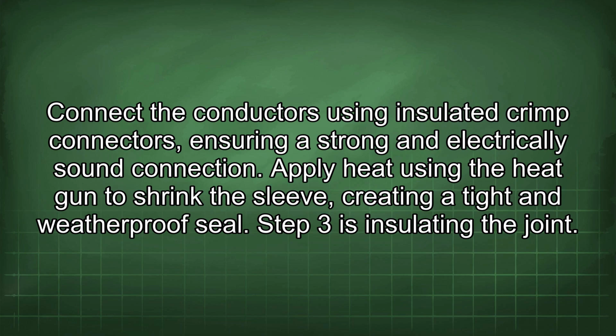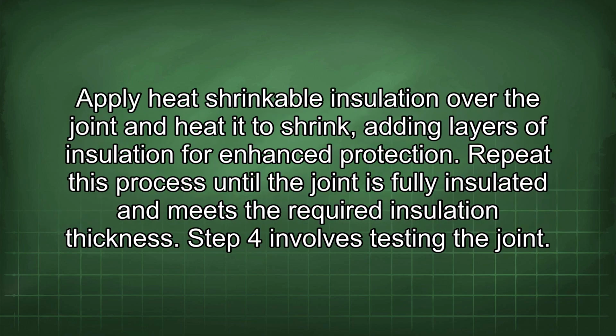Step 3 is insulating the joint. Apply heat-shrinkable insulation over the joint and heat it to shrink, adding layers of insulation for enhanced protection. Repeat this process until the joint is fully insulated and meets the required insulation thickness.